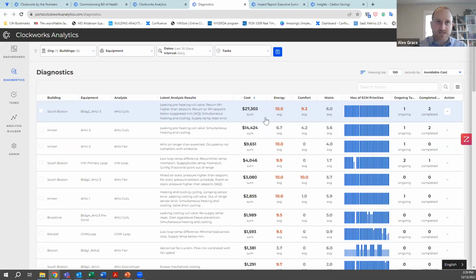So what's been found here specifically is a leaking preheat coil valve, a return relative humidity that's higher than set point, a return RH set point that's below suggested minimum. We've got simultaneous heating and cooling going on and supply temperature reset errors.